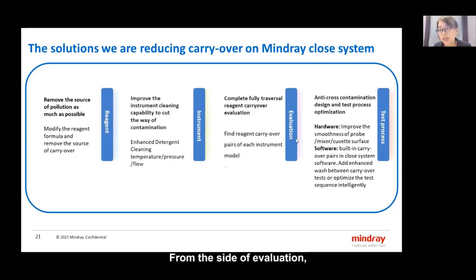From the side of evaluation, we are going to do a more complete, fully traversal reagent carryover evaluation, to find carryover pairs for each instrument model. And from the side of test process optimization, on hardware, we are going to improve the smoothness of the probe/mixer/cuvette surface, etc. And on the software, we will build in carryover pairs in close system software and add enhanced wash between carryover tests to optimize the test sequence intelligently.